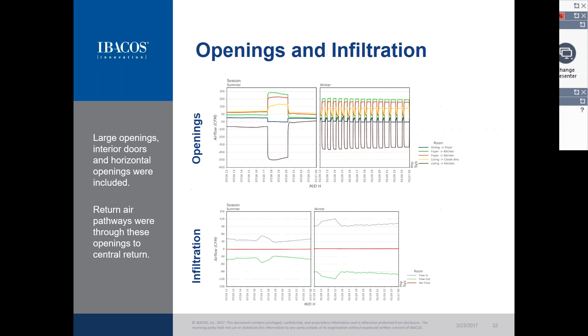That might be a little bit high compared to targets today, but from our experience, field installed duct systems have much higher external static pressure than they're designed for. That's for a number of reasons, and we think that this system has the ability to be much more predictable in that total static amount. So an ideal trunk and branch system, when installed perfectly, could have less static pressure and less fan power than the plug-and-play system. But when we look at real-world scenarios, the plug-and-play system has the ability to be much more reproducible. And so we can dial in that static pressure and, by varying the size of that duct, dial in that sweet spot. And we've found that somewhere around 3 inches provides a good balance of airflow and static pressure.